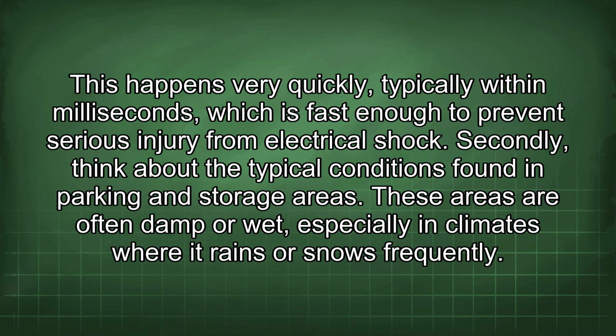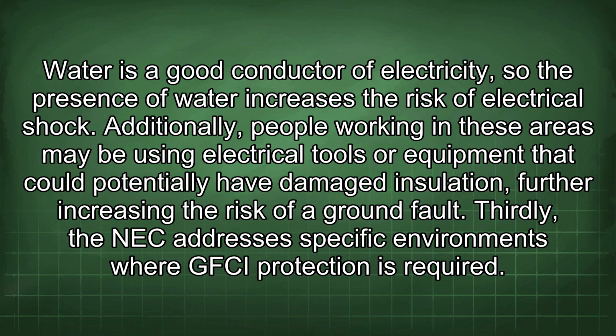Secondly, think about the typical conditions found in parking and storage areas. These areas are often damp or wet, especially in climates where it rains or snows frequently. Water is a good conductor of electricity, so the presence of water increases the risk of electrical shock. Additionally, people working in these areas may be using electrical tools or equipment that could potentially have damaged insulation, further increasing the risk of a ground fault.